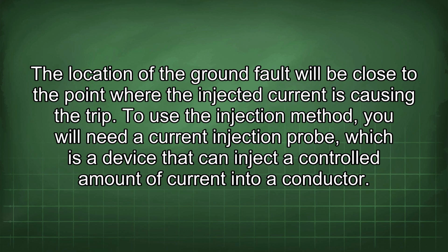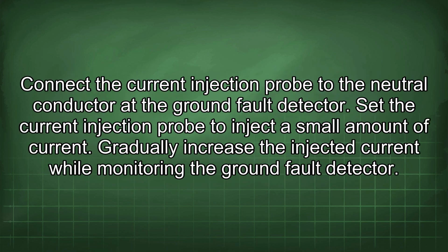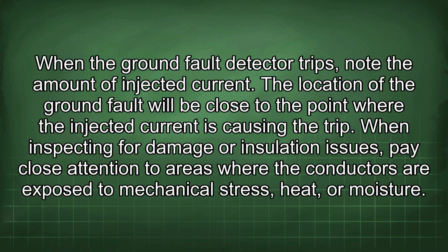To use the injection method, you will need a current injection probe, which is a device that can inject a controlled amount of current into a conductor. Connect the current injection probe to the neutral conductor at the ground fault detector. Set the current injection probe to inject a small amount of current. Gradually increase the injected current while monitoring the ground fault detector. When the ground fault detector trips, note the amount of injected current. The location of the ground fault will be close to the point where the injected current is causing the trip.